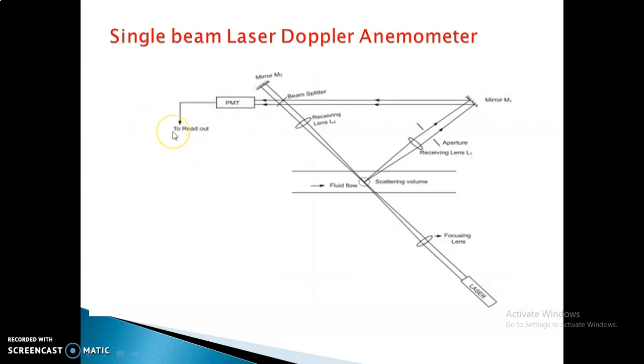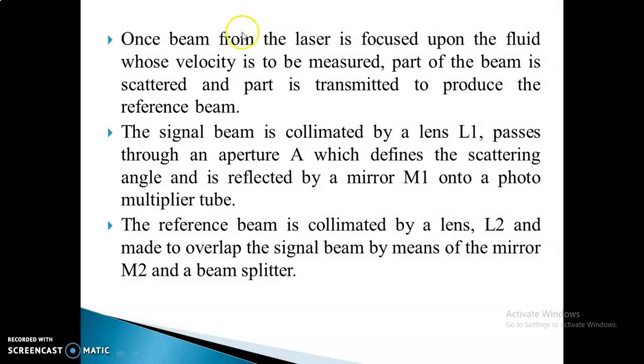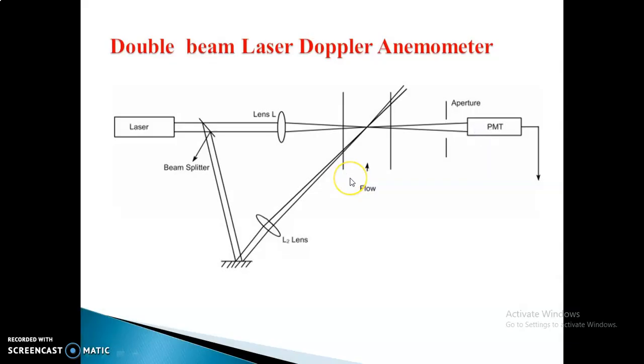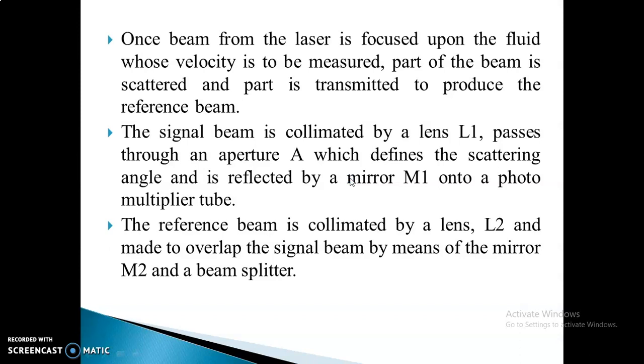Having both the reference and the scattered signal allows us to calculate the frequency shift. The scattered signal is received through the PMT and we can read out the output value. One beam from the laser is focused upon the fluid whose velocity is to be measured. Part of the beam is scattered and transmitted to produce the reference. The signal beam is collimated by lens L1, passed through aperture A which defines the scattering angle, and reflected by mirror M1. The reference is collimated by lens L2 and made to overlap by means of mirror M2 and a beam splitter.